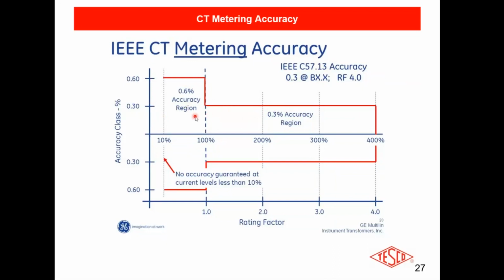Got a question. What happens with a CT if you go above 400% or above the rating factor? So again, if you go above the rating factor, it's a thermal rating factor. You start to heat up the wire. As you heat up the wire, that copper wire, which is typically copper, not always, starts to expand. As it starts to expand, it's encased in insulation. If you heat it up too much, what's going to happen is it is eventually going to break down that insulation.